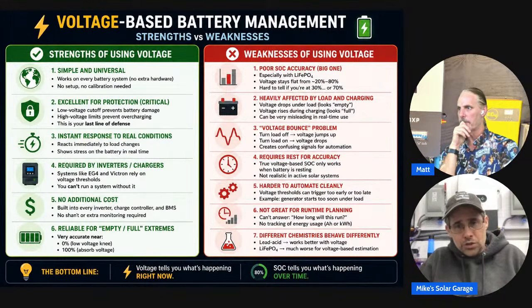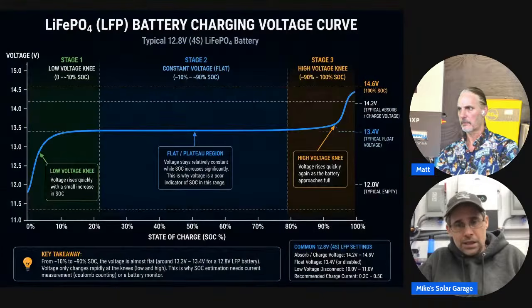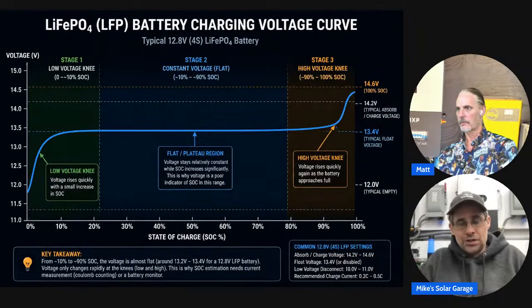So poor SOC accuracy, especially with LiFePO4 batteries, so LFPs. If you look at the voltage, except for the knee, it's pretty much flat the whole way, and it's hard to tell the difference between the states unless you kind of memorize it. There are a lot of good charts you can find online for LFPs that tell you: if you're at 54, you're charged; if you're at 53.5, it's X amount of charge; 53 is Y charge. So it gives you a good idea of where it's at using voltage.